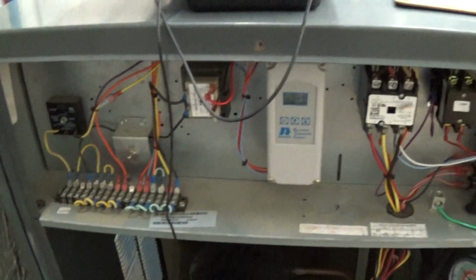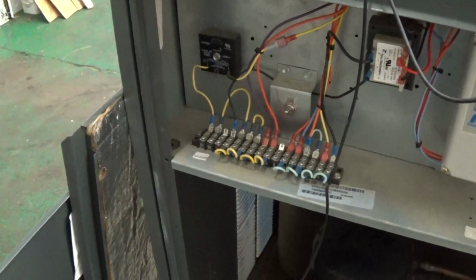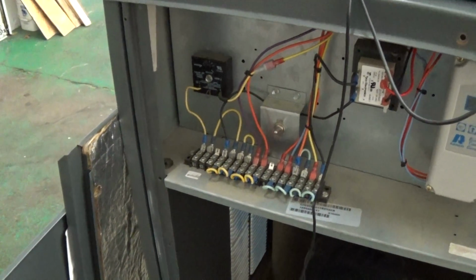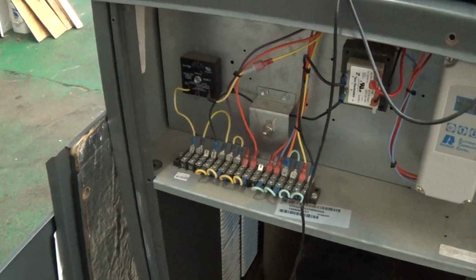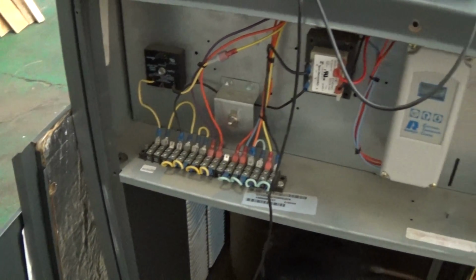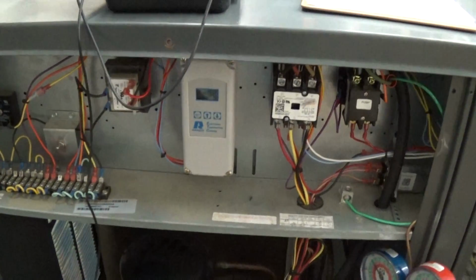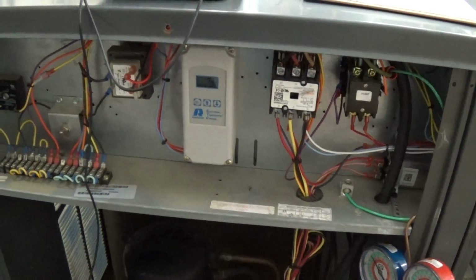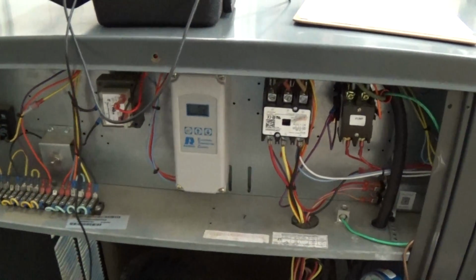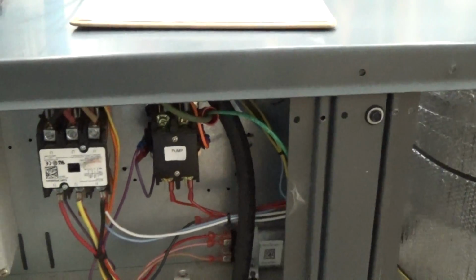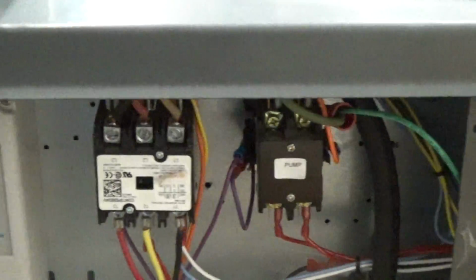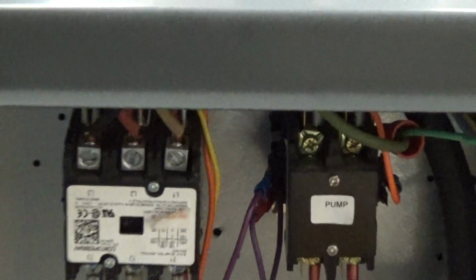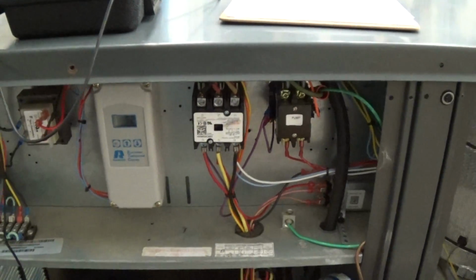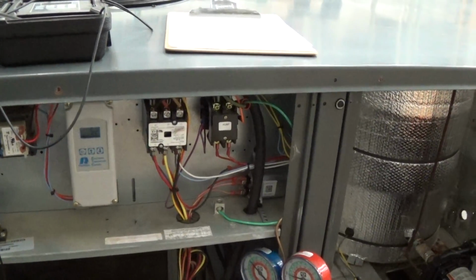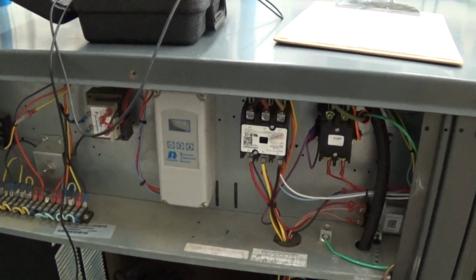Because this is a lower temperature application, I would not suggest in this case to have that connected to a solenoid valve with city makeup water, because you would be diluting the glycol and bringing it to a dangerous condition. Something like this, you probably want to run at least 30% glycol. You can see right now we chilled down to about 52 so far. That's our pump contactor there. And our compressor contactor. We'll come back to video number 2 in a second as we reach the 30 Fahrenheit set point. Thank you.